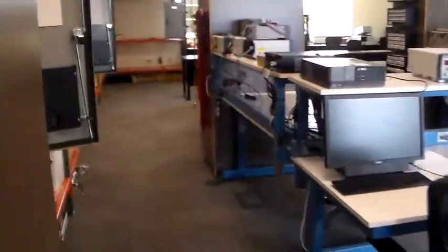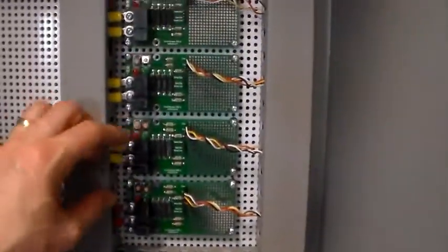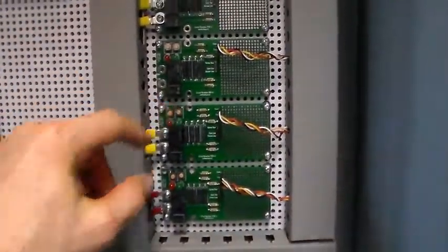Now, of course, shutting the power off is as simple as going in here and then tripping breakers number 5 on junction boxes 1 and 2. So here we go, tripping breaker number 5 on JB1, and over here, tripping breaker number 5 on JB2. That shuts off power to the West and East cabinets respectively.